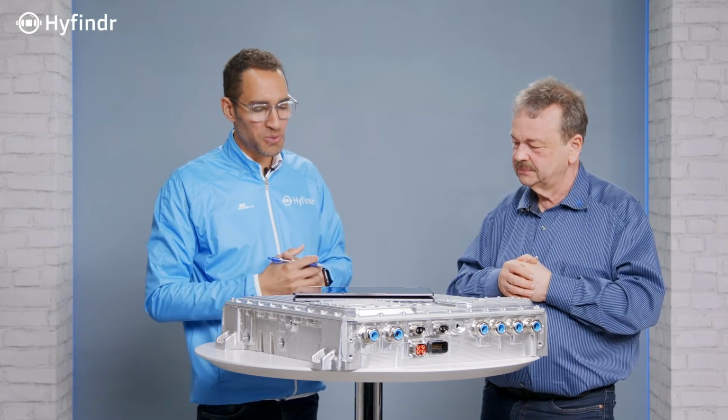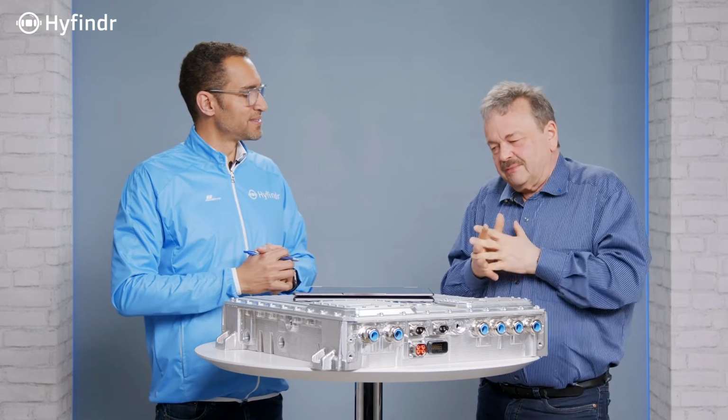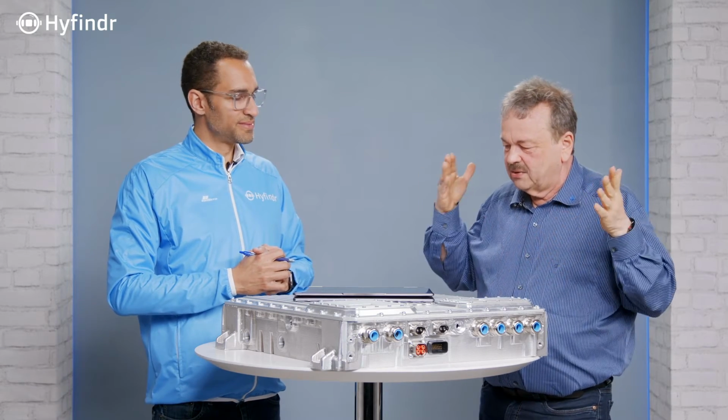Is there more to know? Yeah, what we see as a trend, because the current goes up and up, we see fuel cells on the markets, they will reach, let's say, 900 to 1,000 ampere in the near future. So you must offer a scalable solution, and at 1,000 ampere, you cannot use this kind of cables. So you need copper rails.